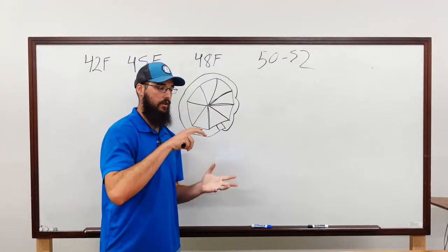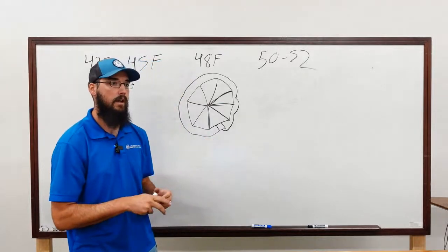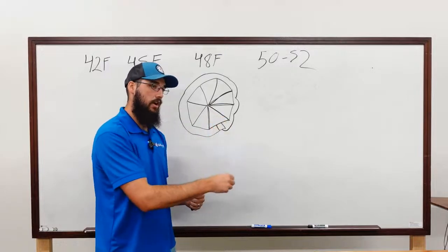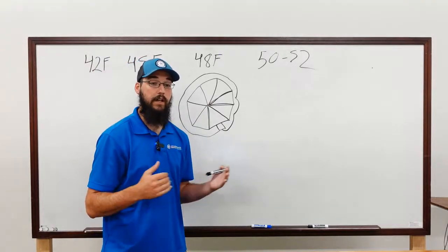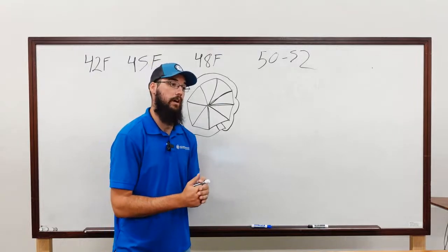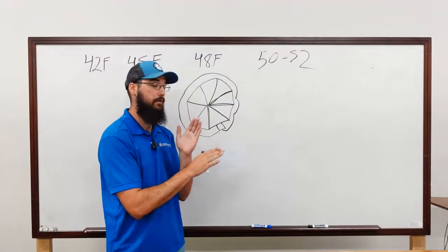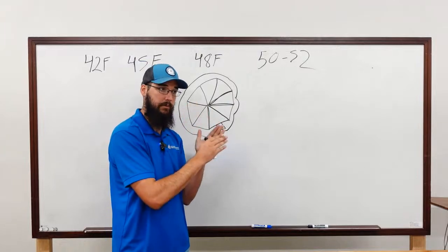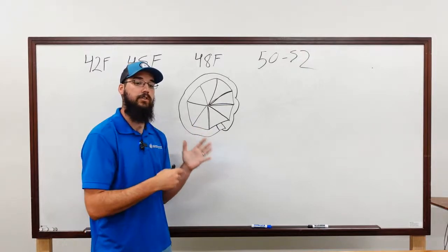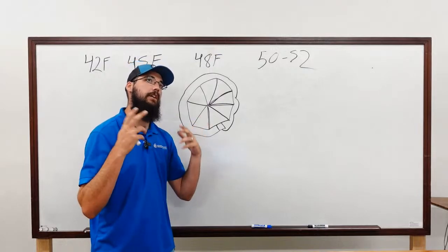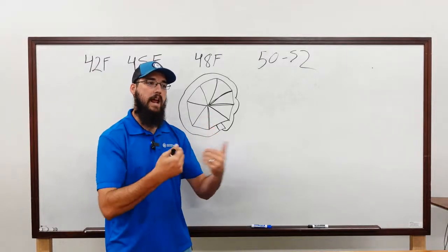So centrifugal impellers require a lot of torque to start them and make them turn on. And if they have any kind of a load on them, then it's going to overload the electrical system on that chiller and on that building. It can't do it. It's too much. So one of the benefits of the IGV, and it's the reason why these have to close to such tight parameters, is when they close off and they're blocking that refrigerant from hitting that nose, there's nothing to pump. So essentially you're almost dry running, which is not a really great way to say it, but you could think of it that way. You're dry running that impeller to where it doesn't have anything to input into it.